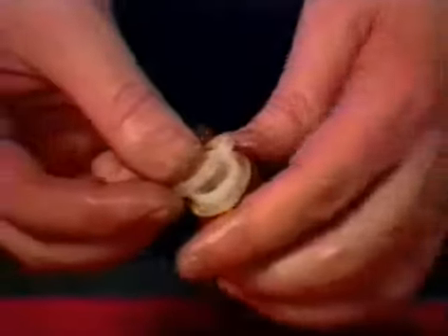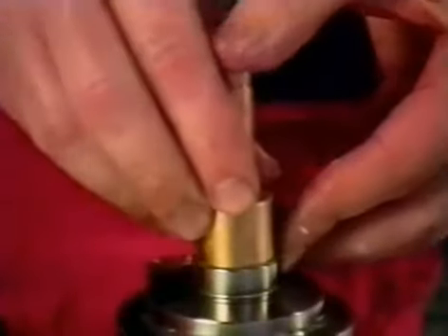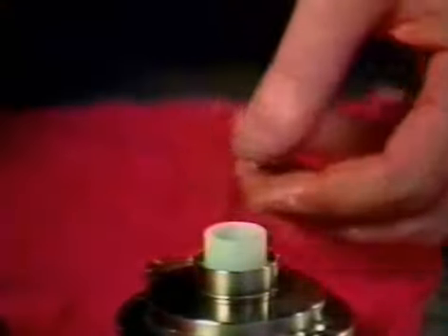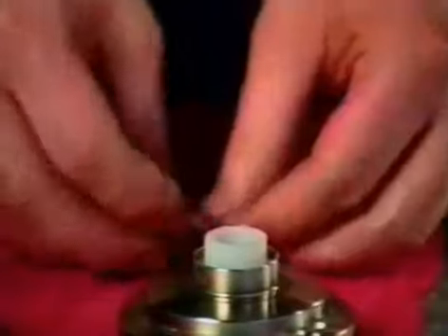Place the dynamic seal inside the installation removal tool and install the lip seal over the dynamic seal with the lip facing toward the tool. Using the tool, install the dynamic seal and lip seal into the backup ring housing. The lip on the lip seal should be facing up when it's installed in the backup ring housing. Remove the tool and press down on the dynamic seal to be sure it's seated against the backup ring. Install the U-cup spacer slots up over the dynamic seal.